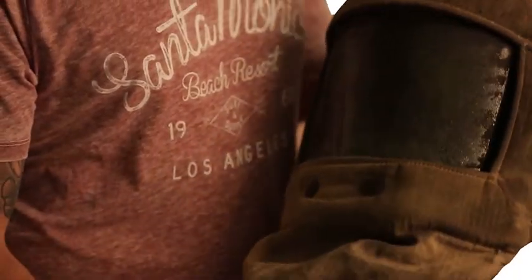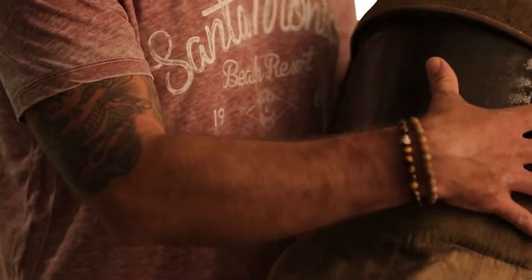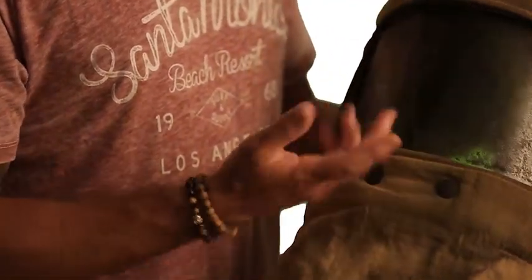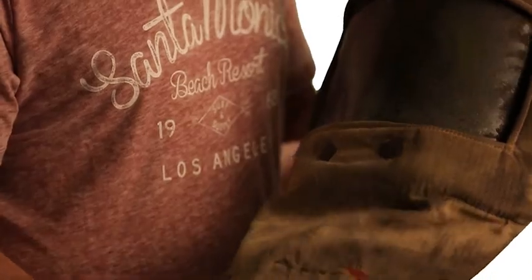The jacket had some burn marks and the cuffs were melted a little bit. This is the arc flash hood I was wearing during the incident. Most of the arc flash blast was directed toward the left side of the mask, as I was facing in at an angle. There's just a little bit of carbon exposure, some melting, some pitting, and metal pieces in the face shield. If I would have had the flashlights we have now on our helmets, I would have just used that — and I've already been using the new helmet with the flashlight and I do like it. It's very helpful.